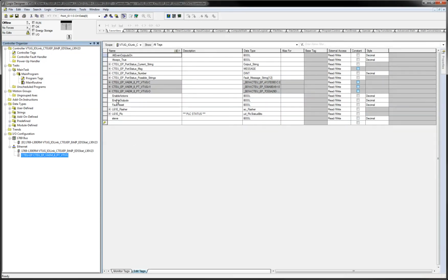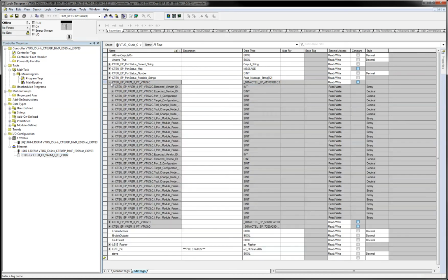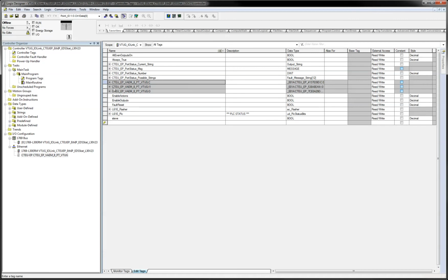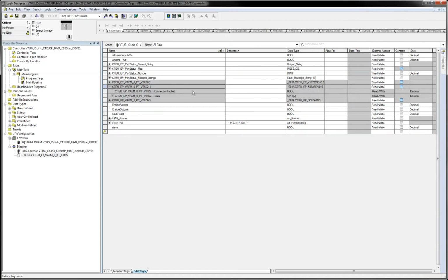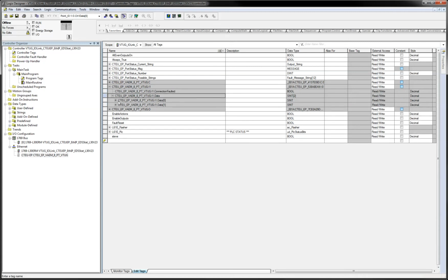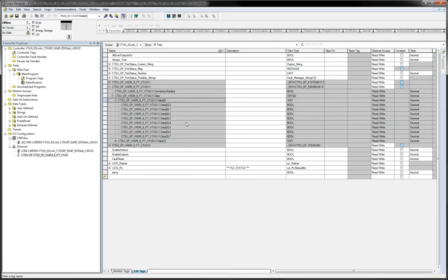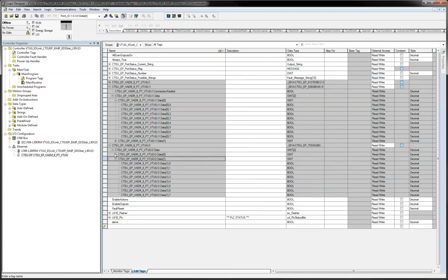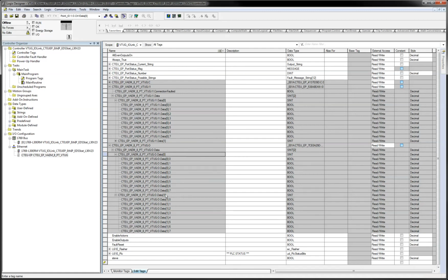When you add this module here, it basically adds based on what we've just done there. There's a configuration word due to the EDS file, and there is a status of the connection itself. There is input data, and there is output data. Now, this particular thing is only an 8-point module. That's because that's how it works.